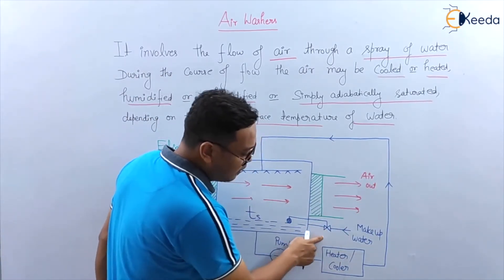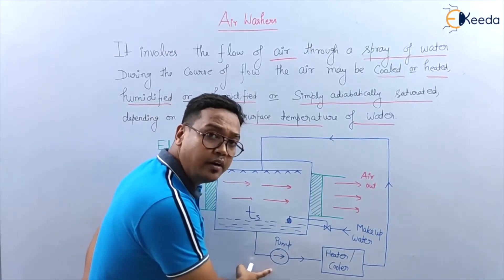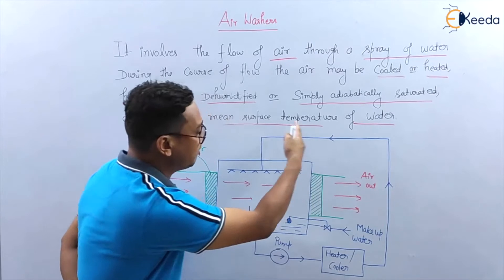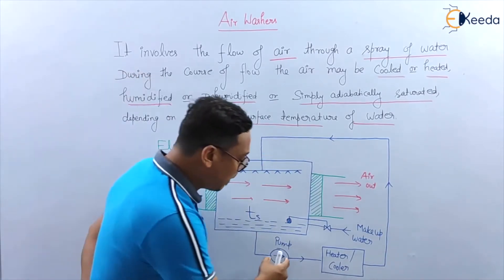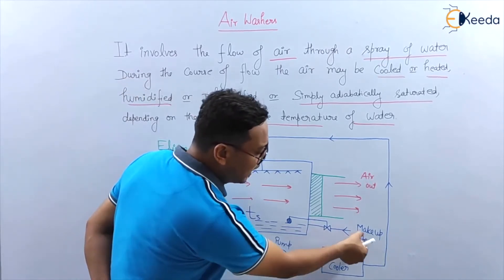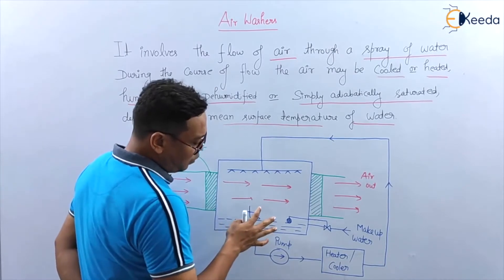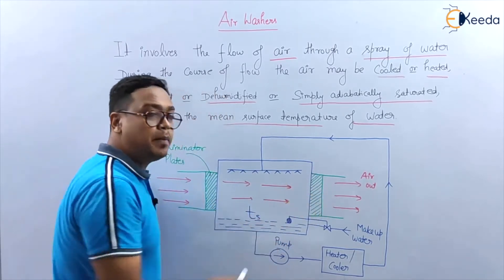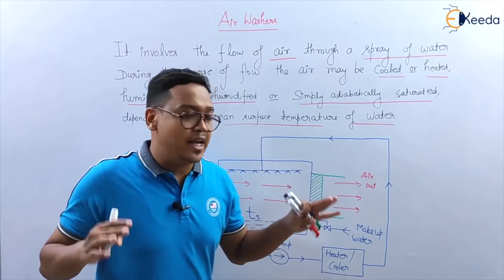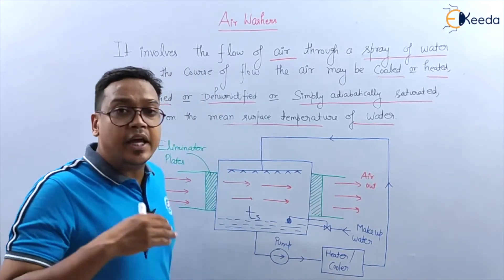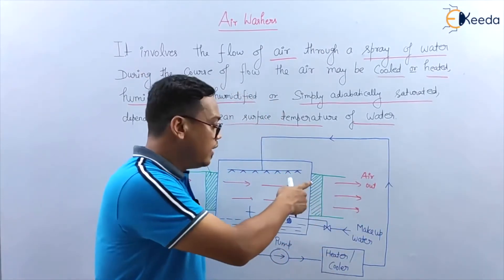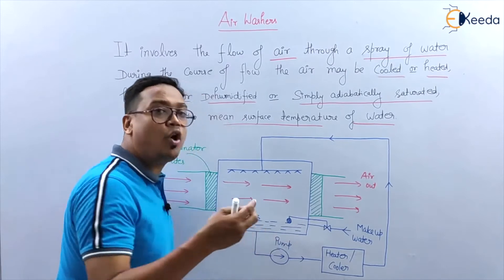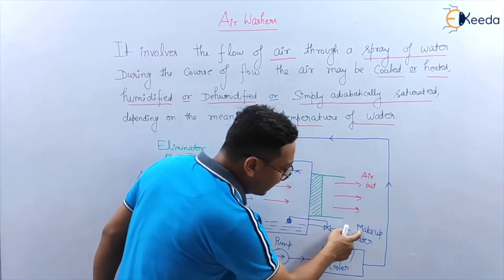This one is the makeup water line. The pump is called a recirculation pump because this water is sprayed, then collected, and again sent back to the sprayer. This is the makeup water. Since the air will carry some water outside and the eliminator plates are not 100% efficient, water quantity in the air washer will go down — that's why this makeup water is used.